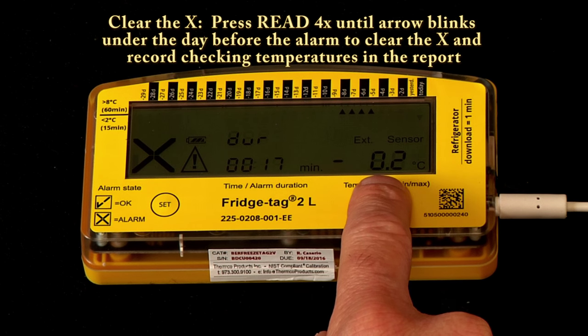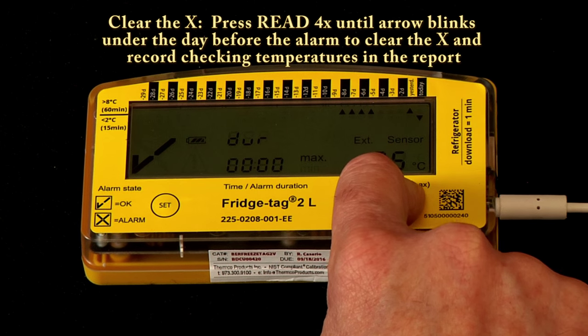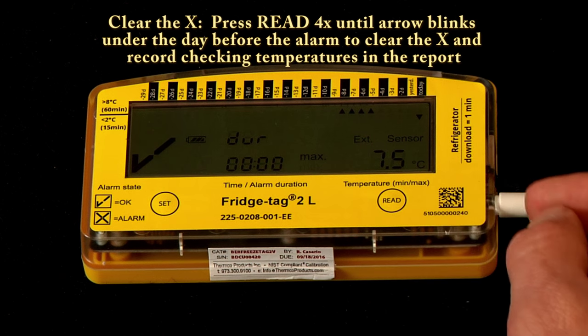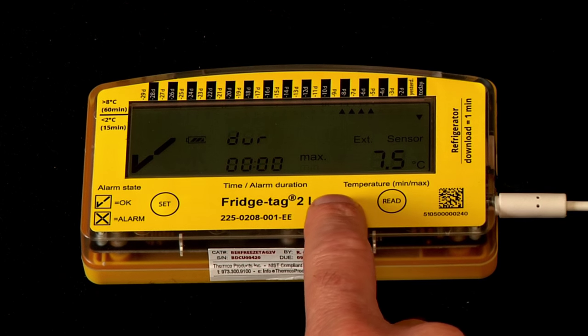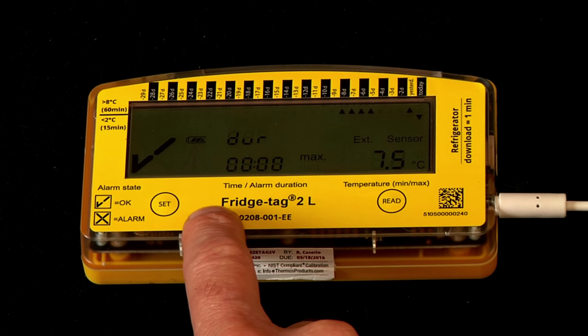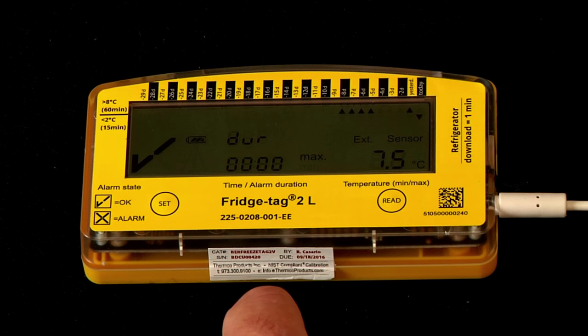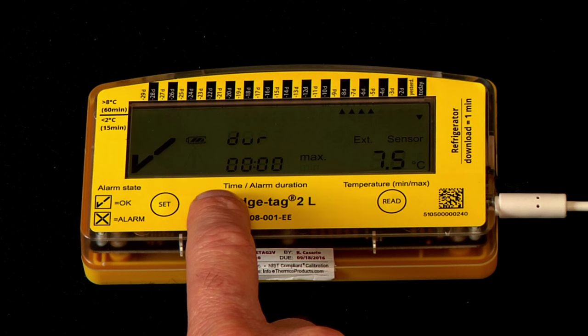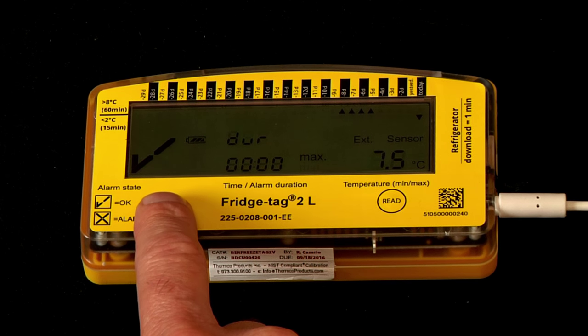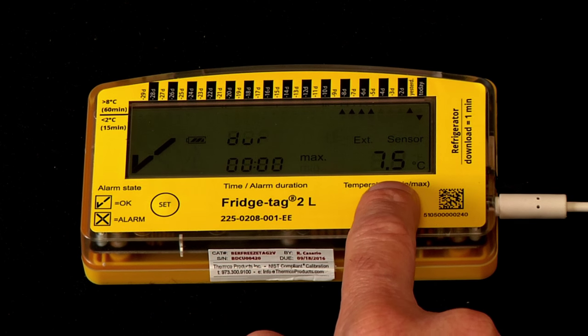When we press it the third time, the duration of that alarm was 17 minutes and the lowest temperature observed during that time was negative 0.2 degrees C. When we press it the fourth time, it commits to memory that we've checked the alarm, the date and time, and it also clears the X. This X-clearing capability is part of all Fridge-tag 2L products and every Fridge-tag sold after the fall of 2014. Pressing set takes you back to current status mode and the current temperature.